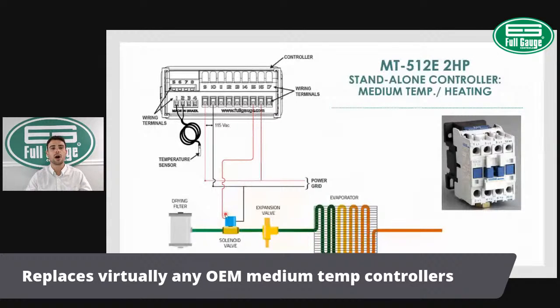Let's say we had to wire this 512 in 220. I would again bring the neutral on terminal 10. That doesn't matter. You can actually feed terminal 10 or terminal 9. But in this case, we are feeding the neutral on terminal 9 and bringing the hot line on terminal 10. But if you want to power in 220, you're going to bring the hot on terminal 11. Terminal 11 is for 220. So it would be 9 and 11 for 220 volts.